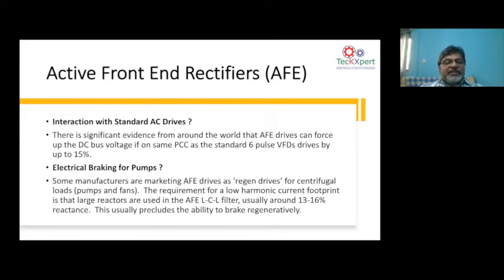Interaction with the standard AC drive. There is significant evidence from around the world that active front-end drives can force the DC voltage. It can increase the DC voltage. These are some of the issues with active front-end drives. So my discussions are now to compare the technologies. So I will not spend too much time on this.